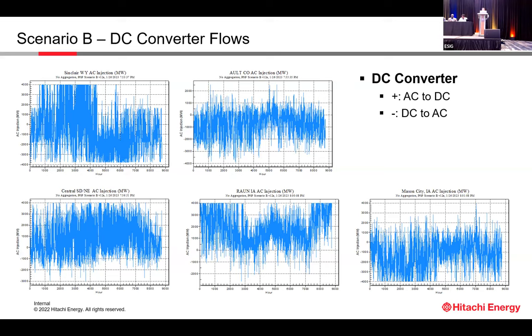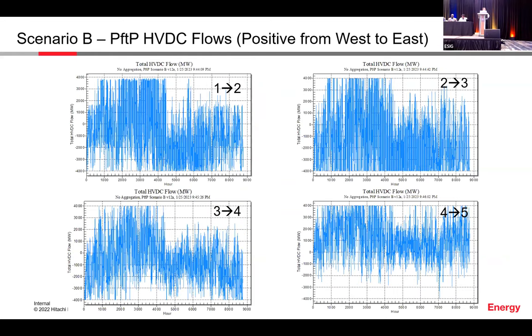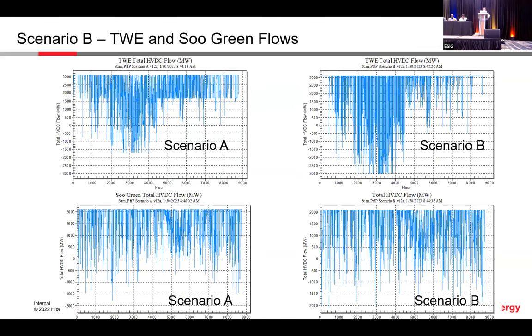There are a couple of other things you can look at, the individually optimized converters. Then you can look at the transmission line. Because this is a radial connection, it goes 1 to 2, 2 to 3, 3 to 4, 4 to 5. You can see the DC line utilization compared with scenario A and scenario B. Scenario B is building the bridge between the east and west.